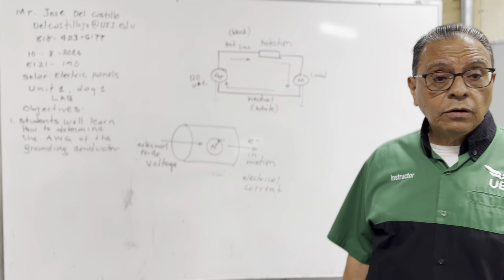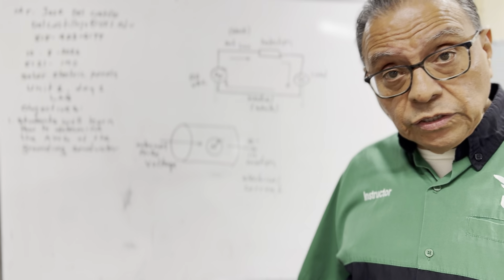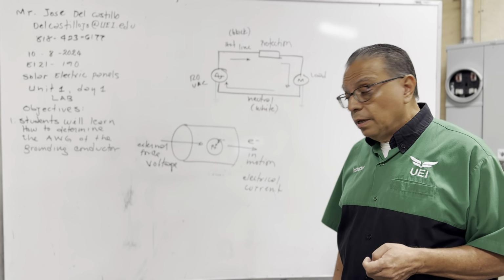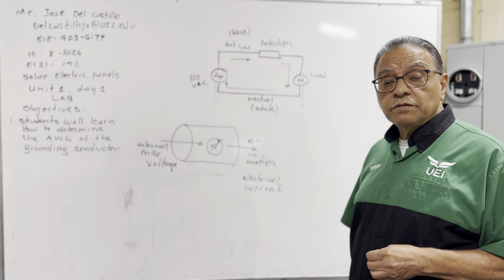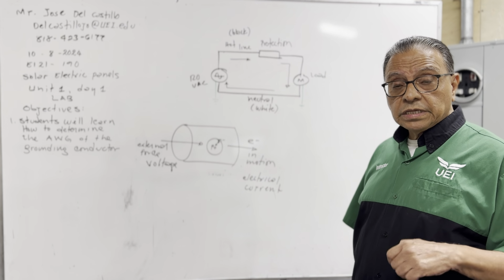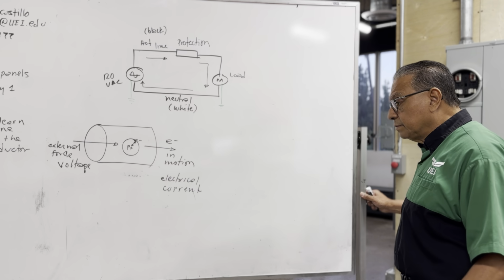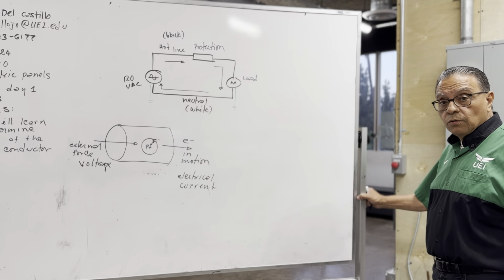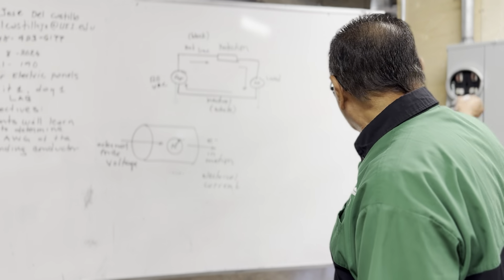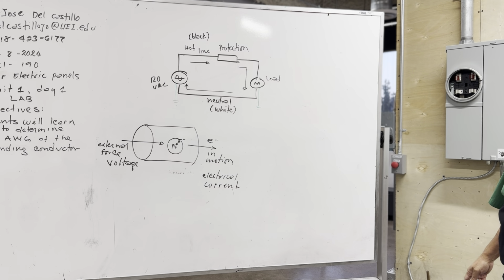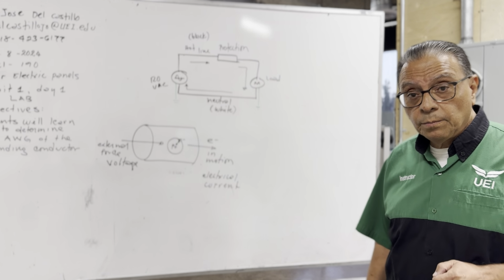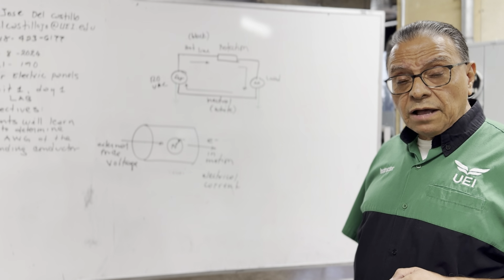So we are going to use a dwelling unit as an example. My dwelling unit has 1,350 square feet. We are going to start working with this as an example to determine the gauge of my grounding conductor, and then I will show you on the service panel. This is a service panel. As I told you, a service panel is an electrical panel at which the service company delivers the power, and it's the only place in a dwelling unit in which we have to have a grounding system, a ground. So we are going to use this service panel as an example, and the dwelling unit that we are going to use is 1,350 square feet.